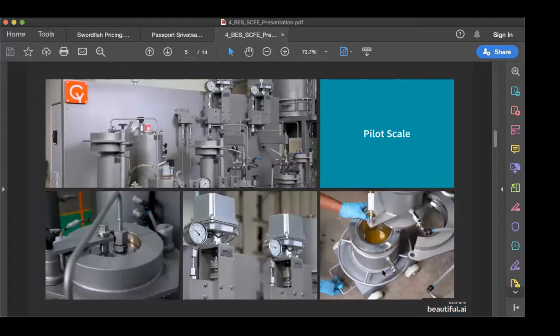Like I said, pilot scale to production scale. What you see here is overall a pilot scale system where you have 2 extractors, your back pressure regulators, and your separators. We've got a very unique separator design where even if you have very high resinous products, you can detach the entire separator bottom so you can collect the oil much easier.